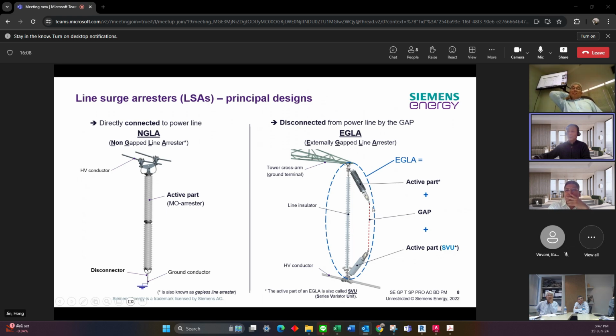In the middle, we have a certain gap. This is an air gap, and in normal conditions without overvoltage, this air gap avoids leakage current, because no current passes across the surge arresters. Only under a lightning strike, when the overvoltage comes, will this air gap be sparked over by the high voltage from the lightning. Then the surge arrester will bypass the energy, and the arcing current goes from one surge arrester at the middle to the other side.